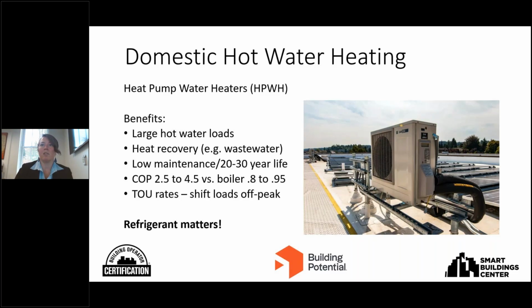Again, high COP, anywhere from about 2.5 to 4.5. Traditional boiler efficiencies are about 0.8 to 0.95 for the most efficient condensing boilers, which actually aren't always running in the condensing range, so typically they average lower than that.